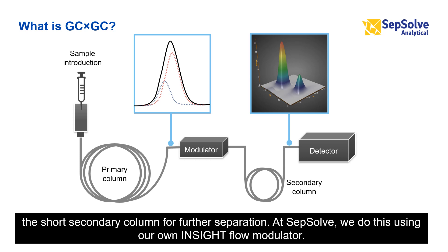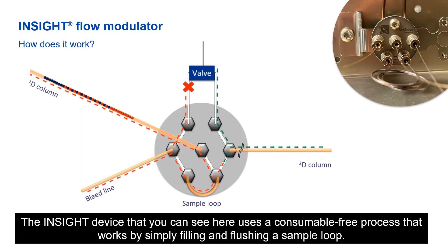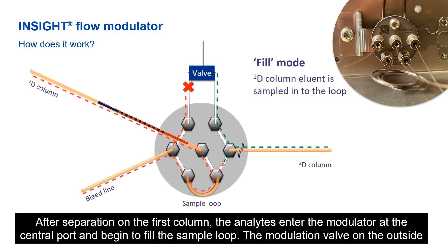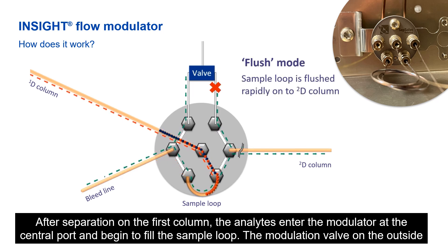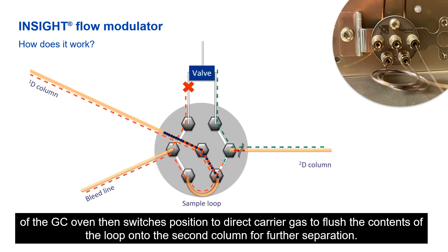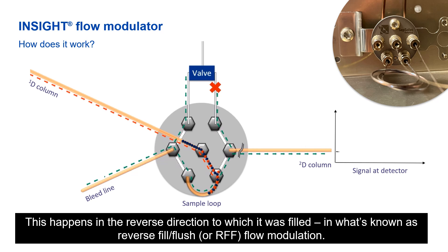At SepSolve, we do this using our own InSight Flow Modulator. The InSight device that you can see here uses a consumable-free process that works by simply filling and flushing a sample loop. After separation on the first column, the analytes enter the modulator at the central port and begin to fill the sample loop. The modulation valve on the outside of the GC oven then switches position to direct carrier gas to flush the contents of the loop onto the second column for further separation. This happens in the reverse direction to which it was filled, in what's known as reverse fill flush, or RFF flow modulation.